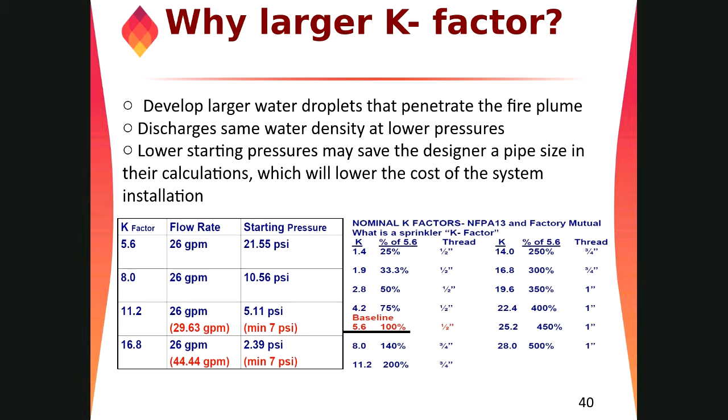We calculated that the minimum we need is 20 psi based on our theoretical calculation. But we understand that in a fire protection system the pressure will never be exactly what we determined. The pressure will be based on the flow requirement from the fire pump, so it will go a little higher than that. We need a minimum of 20 psi. This is our bottom. Higher is fine, we don't have any problem with that.